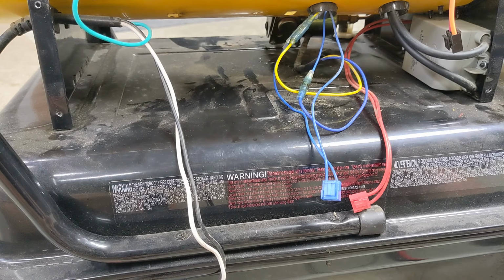Because if they reset, as the temperature went back down, I think they'd come back on. If the thermal overload tripped but cooled back down, everything would come right back on. Let's say the fan failed, so it's no longer blowing air, but it keeps squirting fuel in there and the igniter's going. That's bad juju, that would mean all that heat gets stuck in the machine, and we don't want that coming back on. If it trips off, in this setup with the switches, the fan would keep running, but the fuel would shut off.